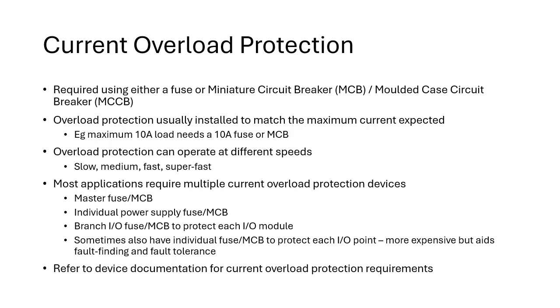But you could go down to individually limiting each I/O point. It's more expensive, but it does aid fault finding and fault tolerance. As an alternative to that, on some particular output modules, you can get output modules with electronic short circuit protection, which might be better than individually protecting each output. But you've got to be careful there, because with an ESCP module, some of them reset when you just turn current off to that individual output. Some of them need the whole module to be power cycled. So again, you can refer to device documentation and look at what the current overload protection requirements are. And it's also based on what you need for your particular application requirements, and also how much money you are willing to spend.